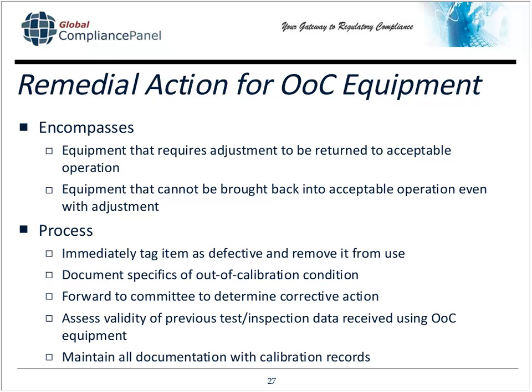So when you determine the specifics of the out of calibration condition, let's say it was 1/1,000,000th out of calibration. Well, you know what? Our tolerances are 1,000th. So the fact that it was 1,000,000th, it's okay. I have then therefore assessed the validity of the previous data and shown that it is acceptable. And all of this remedial action documentation should be maintained with the calibration record for this particular piece of equipment.